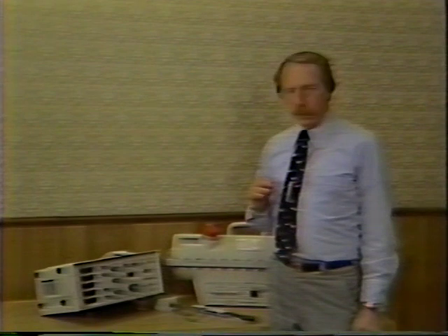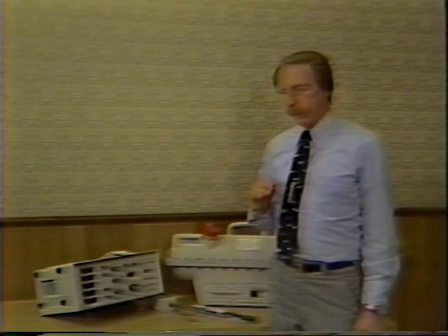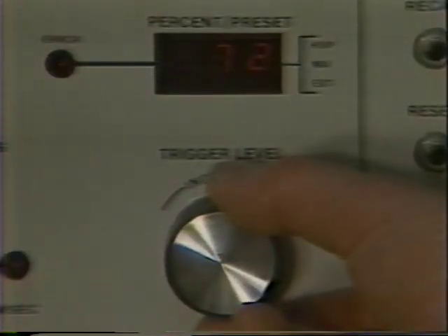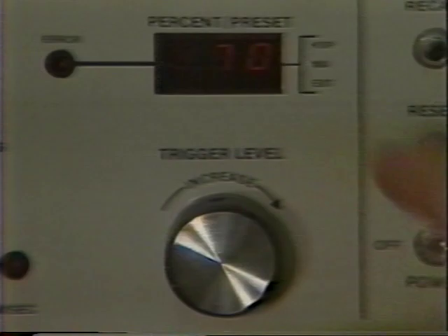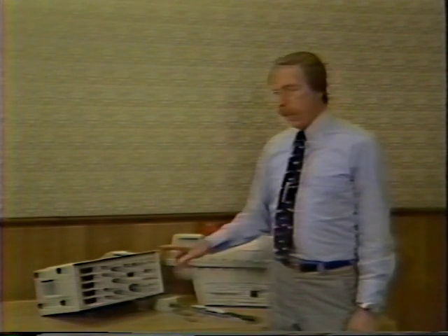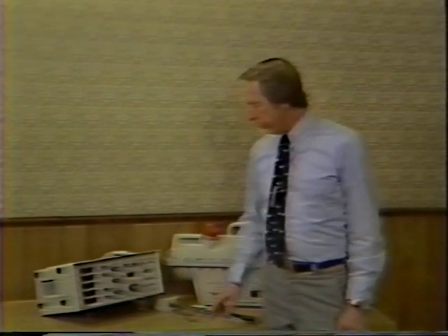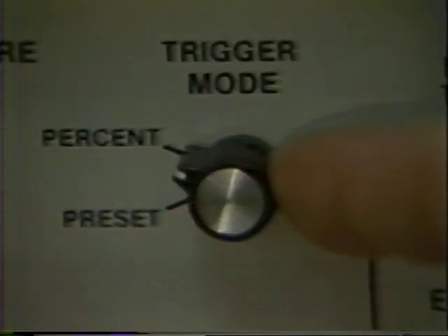If we're in European equipment, we understand Siemens and Philips trigger or measure time at the 70% level. At this point, we would dial back to 70% and use that level. Regardless, we recommend that you consult the manufacturer's manual to determine where they measure time and measure that in the same manner. The next control is the trigger mode switch.